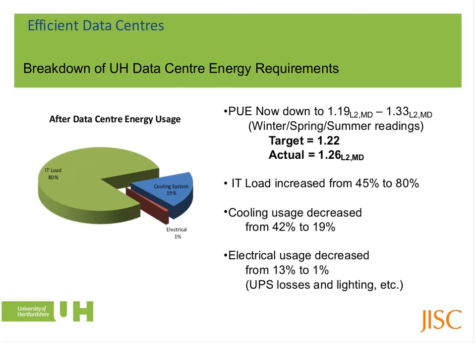IT load, as a proportion of total facility load, went up from 45% to 80% of electrical power usage, and the cooling was decreased considerably down to 19%. So that's where most of the savings came from. Electrical usage was down to just a negligible figure because we were using very high efficiency UPSs.